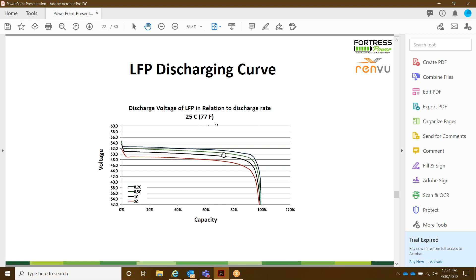What you would do is take a voltmeter and figure out the voltage depending on the C rate to determine the capacity. For example, at 0.5 C, we measure the voltage—let's say it's 50 volts—and we then know the capacity of that battery is at 80%. So that's just a quick tip for measuring the capacity of the LFP 10 or LFP 5 battery.